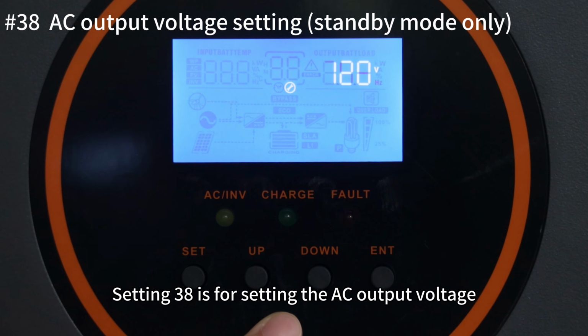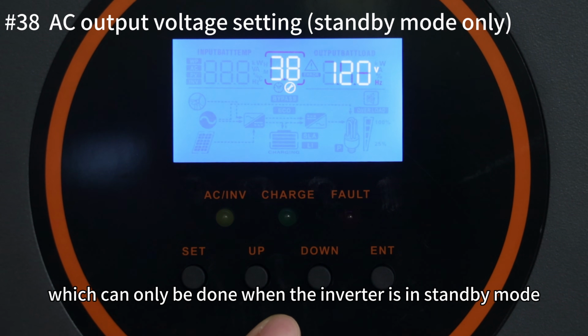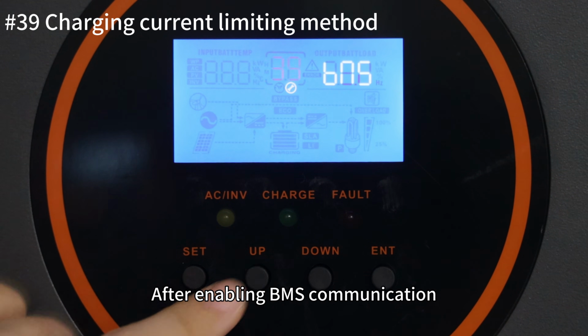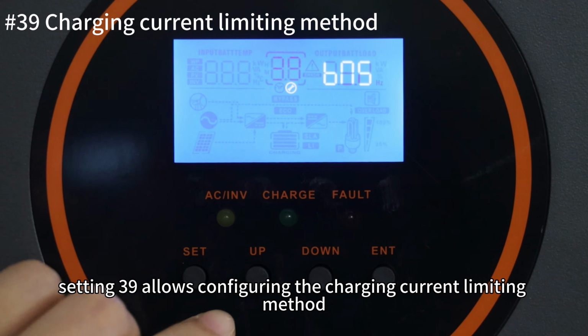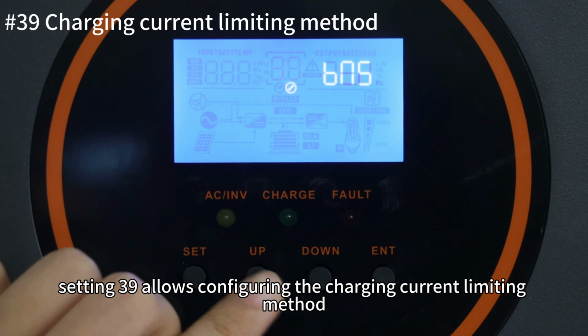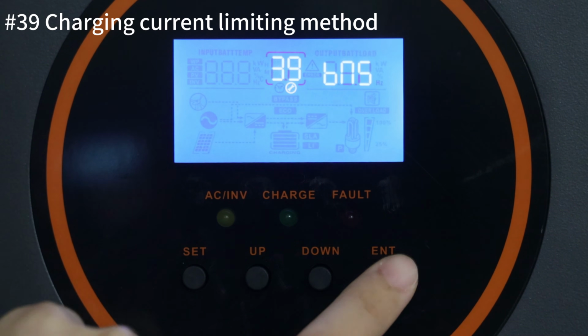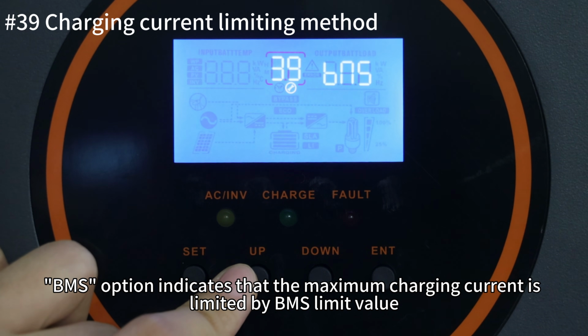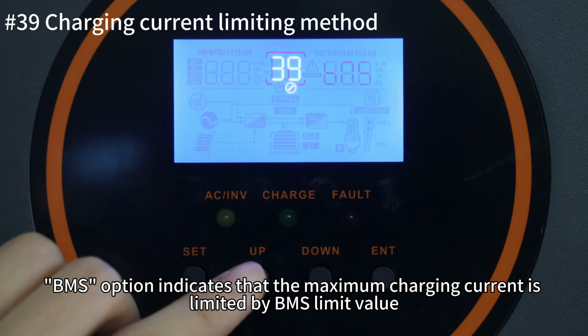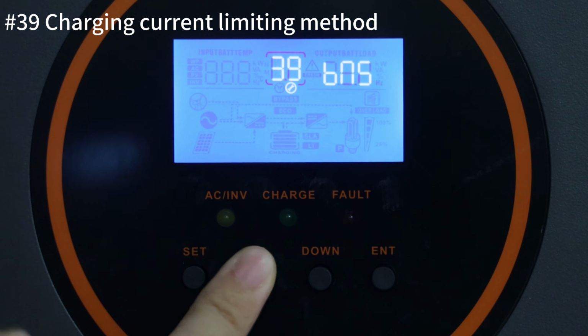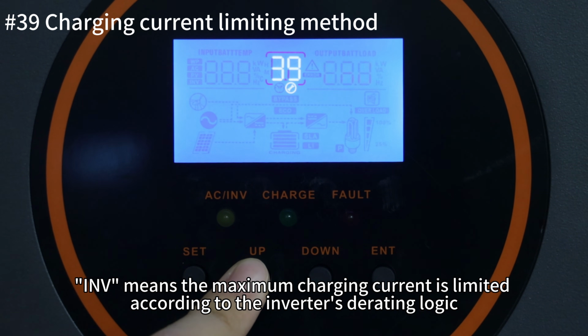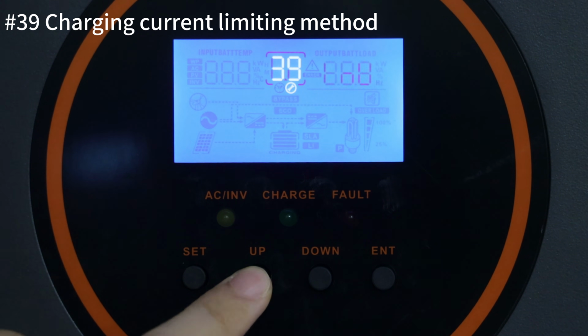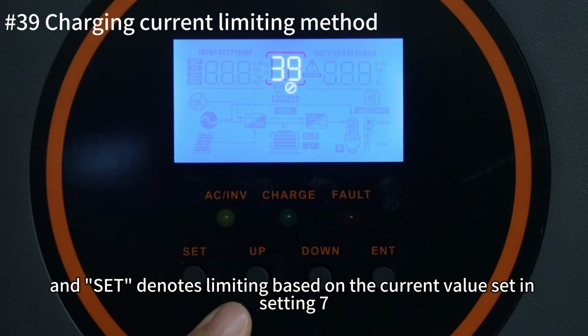Setting 38 is for selecting the AC output voltage, which can only be done when the inverter is in standby mode. After enabling BMS communication, setting 39 allows you to configure the charging current limiting method. The BMS option indicates that the maximum charging current is limited by the BMS limit value. The INV option means the maximum charging current is limited according to the inverter's derating logic. And the SET option signals limiting based on the current value set in setting 7.